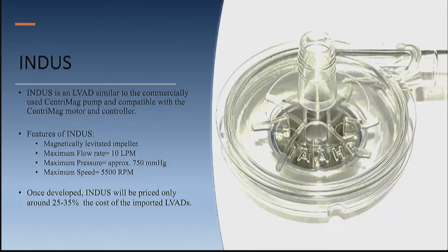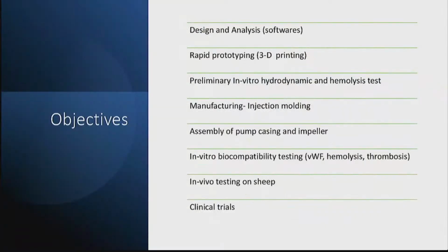So we have developed Indus, a ventricular assist device with a magnetically levitated impeller, with a maximum flow rate of 10 liters per minute, maximum pressure of approximately 750 mmHg, and a maximum speed of 5500 rpm. This is very similar to the already available Centrimag in the market. The cost of this device is proposed to be about 25 to 35% of all the imported LVADs. When we develop any device completely indigenously instead of importing it, the cost drastically reduces.